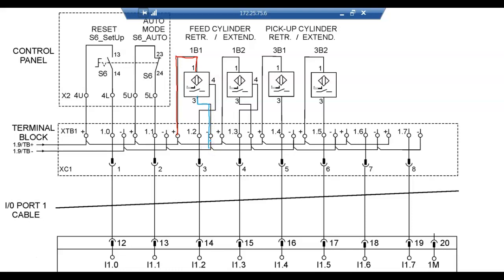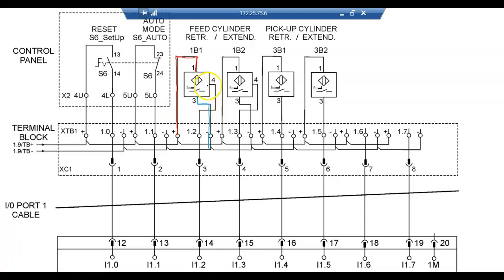4 is the normally open contact, it's going to be the black wire. So that black wire is running, I need to watch out for it. The black wire is running down to 1.2 - so 1, 2, and 3, these are inputs. 4 and 5 - oh, here's a 6, we need to check that out.